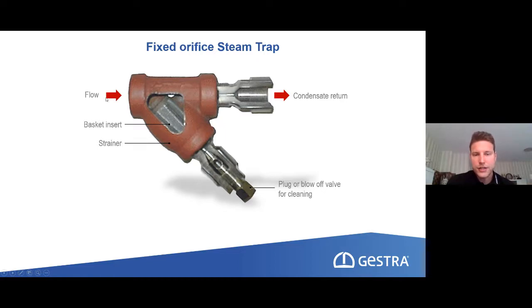So if we have condensate coming inside the steam trap, the condensate is rather dense compared to the steam, so it can travel through the small drilling. But as soon as we have steam, which has a high volume, it cannot pass this easily through this drilling. So it will stay in the system while the condensate can be discharged. But we still have the problem with the air venting, because air also has a very high volume and can also not fit through it. And as soon as air can pass through the hole, then steam will follow directly after that.